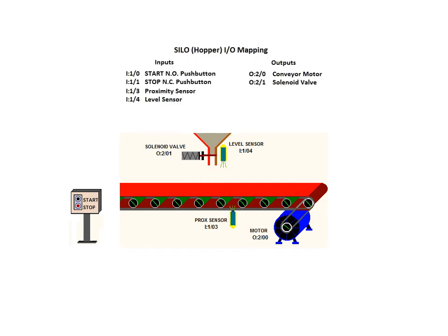We will start by examining the I/O mapping for the silo environment. Bit 0 of input rack 1 is connected to a normally open push button used to start the silo application. A normally closed push button used to stop the application is connected to bit 1 of the I/O input rack. A proximity sensor is being used to detect the arrival of a container at the filling station, and is connected to input rack 1, bit 3. A level sensor is connected to input rack 1, bit 4, and is used to detect when a container has been filled to the desired level.